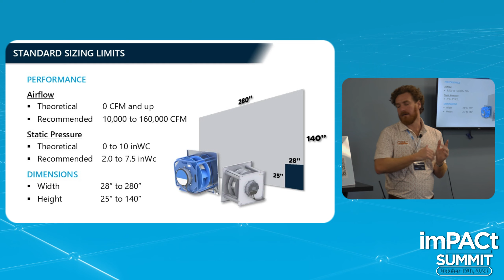There are minimum dimensions here as well, but that's more just for QUIPS. The QUIPS selection tool is the configuration tool we use to do probably 90% of our projects. There are some situations where the project scope is a little outside of that, and there's a feature called a special request, which basically allows you to do something custom. If you're using QUIPS and you can't get a selection, you'll submit a special request, and our product engineering team will see if they can make it work. Sometimes you'll have systems that are below 1 inch of static pressure. That's a case where that comes up. If you have more than 18 fans, that's another one.